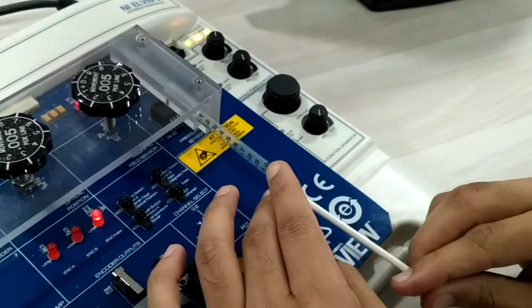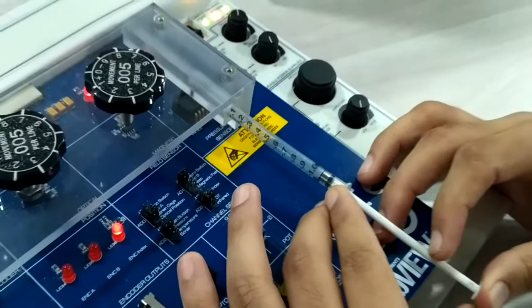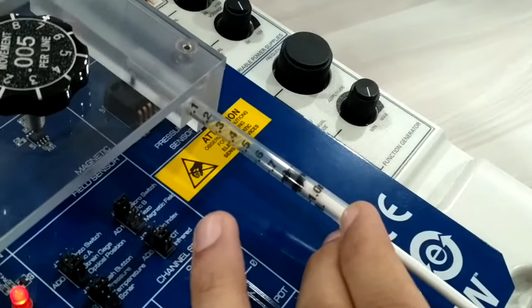Now we'll calibrate our sensor, let me show you how the calibration will be done. As soon as I insert this plunger inside and move it to 1 milliliter, it shows me 0.97 milliliter, so a small amount of error is there. Let me change the value now, let me move it to 0.8. At 0.8 it is showing exactly 0.8.